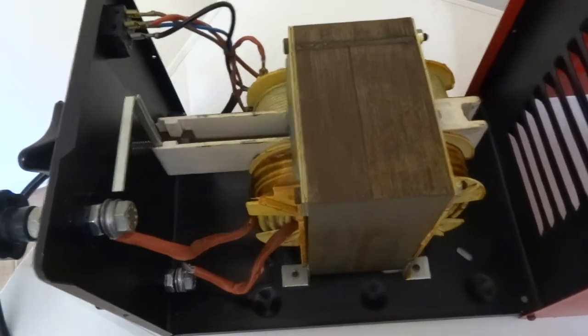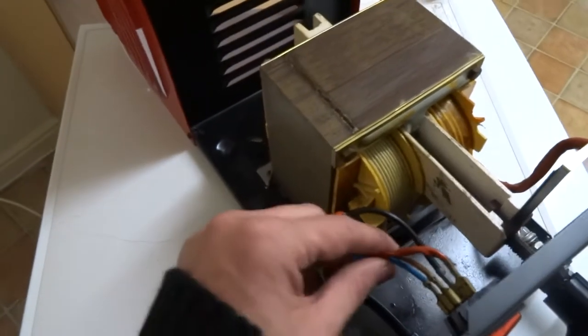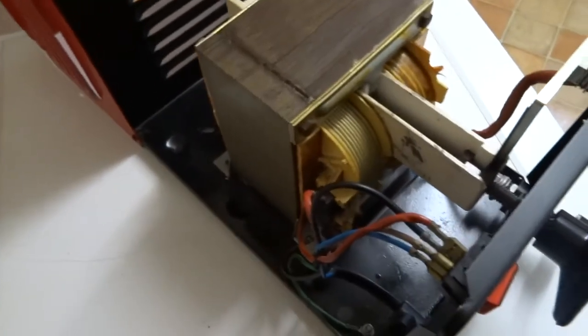So next I'll do a video on how to test them. There ain't much to these so there's nothing really that goes wrong on them. However the coils can split, the wiring splits, connections fail, the switch fails, the thermal cutout can go, or just bad connections all round.